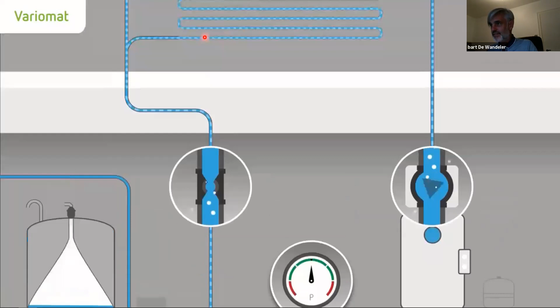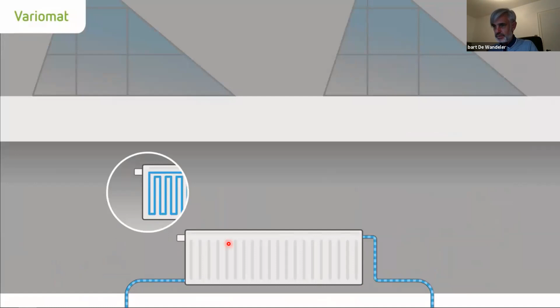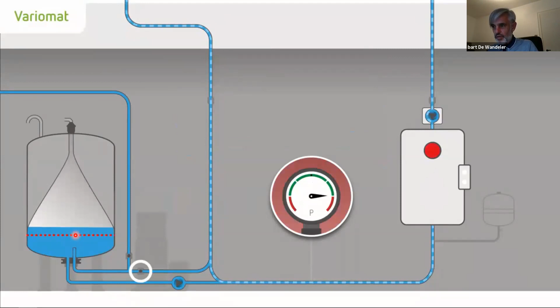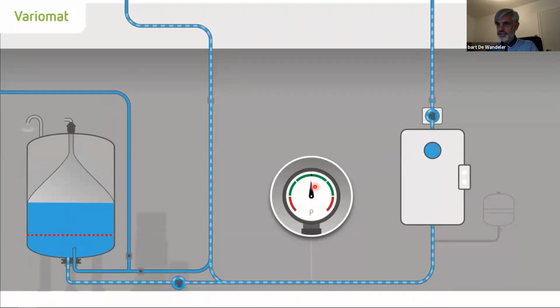What we are going to do, we start the system, this is fully automatic, and we will degas. We will pump water into the vessel, and we go around the system, and we will remove air. Big air bubbles will be removed. Of course, we will also get water drops because we remove air and we make place for water. So that also means that we then have to start a protection to make sure that this water reserve in the system is still available. We can open a valve and we can also put water back into the system. If the pressure goes down and we have less water, this is the next step. This valve will open and city water can go back into the vessel. What we are doing now is the degassing cycle, and we constantly stabilize the pressure in the system.